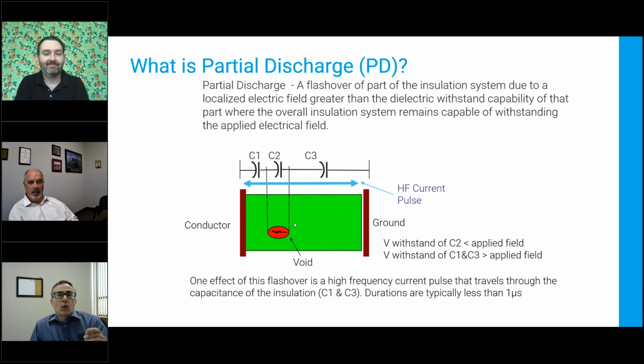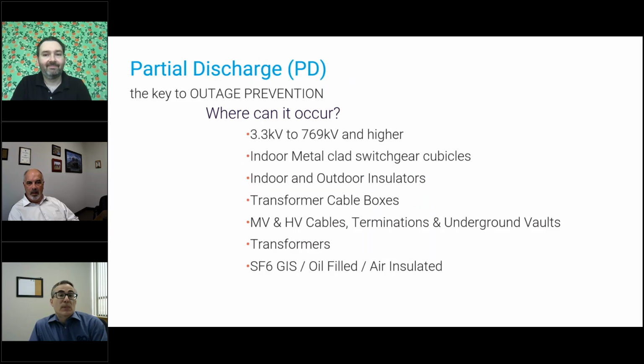However, as the voltage goes up for the 50 or 60 hertz sine wave, you're going to reach a point where the spark's going to jump the gap, just like in the video that I showed you earlier. And every time that happens, twice per cycle, in the positive and the negative half cycle, it's going to eat away a very small amount, but still significant enough that over time you'll have a path, maybe not a straight line, but some path where you'll have a flashover event. And PD is a leading cause of substation failures in a variety of places. What we're mostly concerned with is medium and high voltage. So we say 3.3 kV and up. And then the rest of those bullets are just places where you would find medium and high voltage.